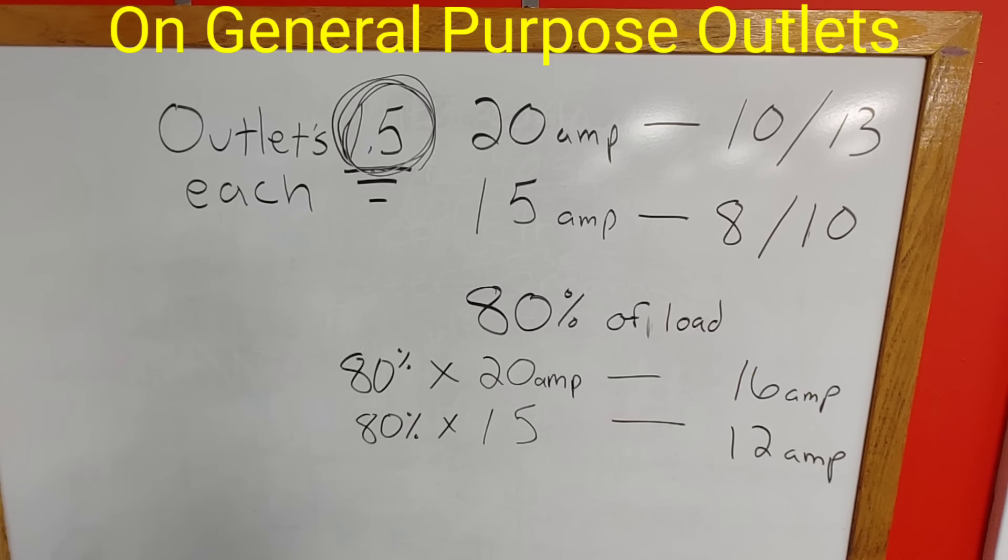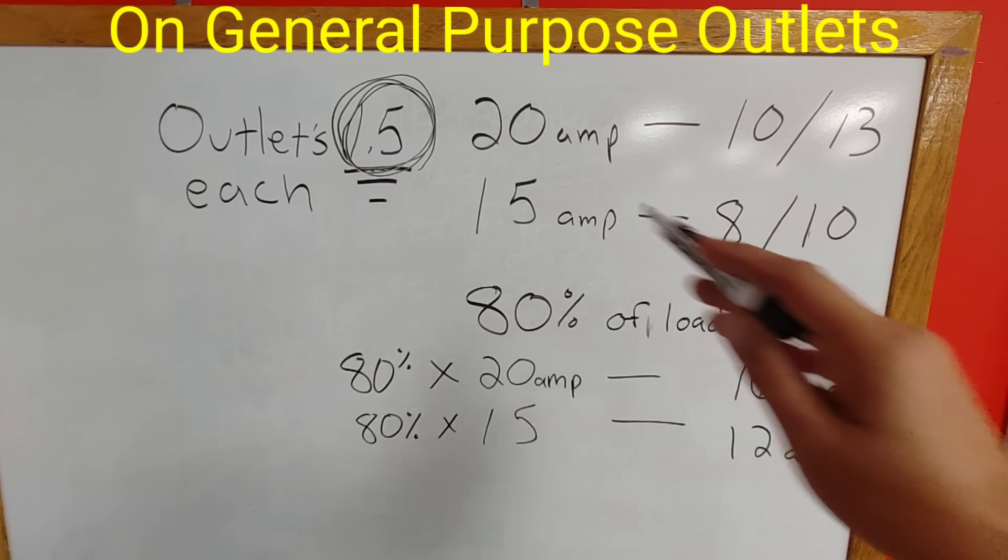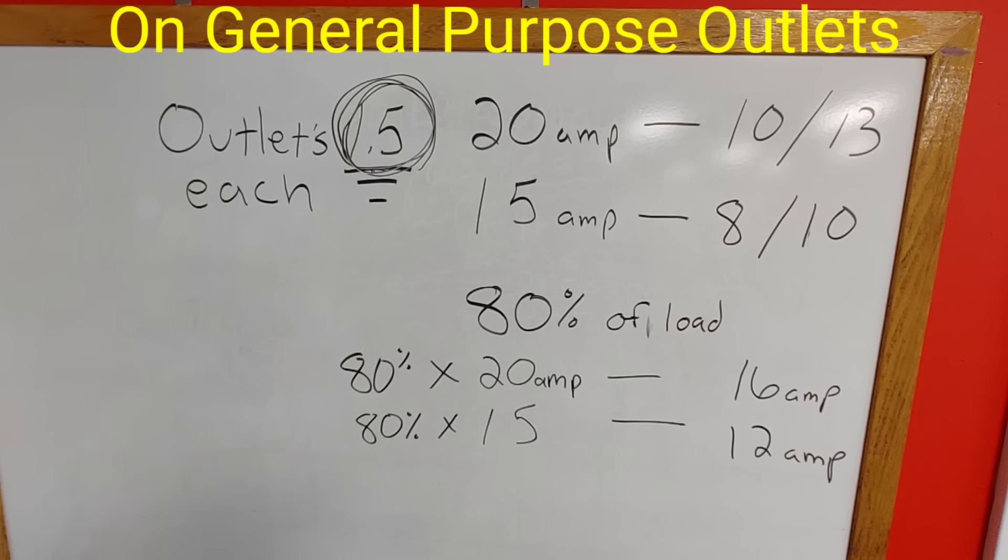Now with that being said, if you have 1.5 amps per outlet and you have a 20 amp circuit, you can actually put 13 outlets on that circuit. And then again, if you have 1.5 amps per outlet on a 15 amp circuit, you can actually put 10 outlets on that circuit. And that is kind of the number that most people will go with.